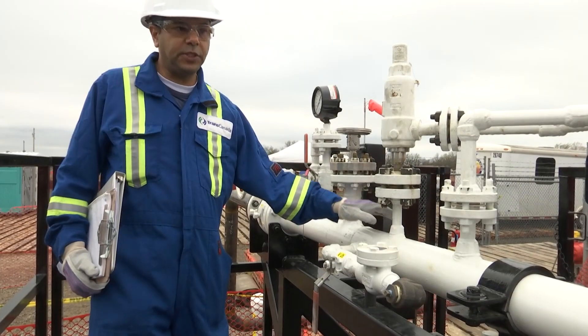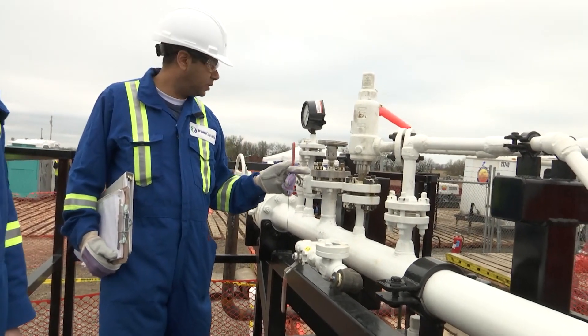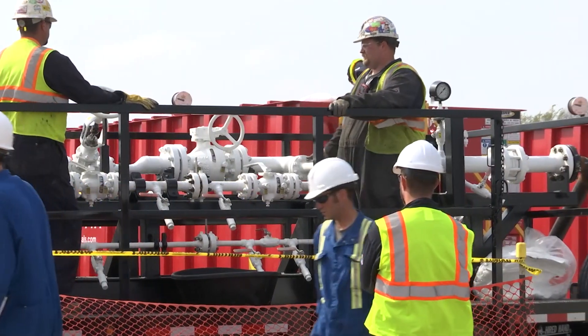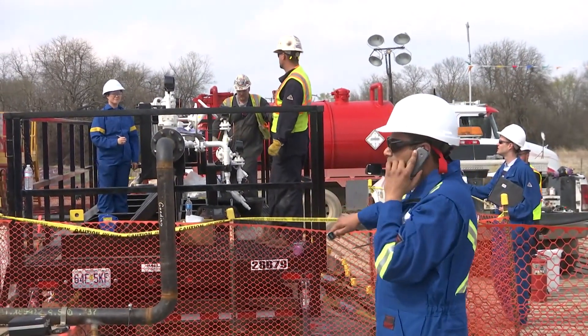When we flow oil, they will see that the oil is leaving the Keystone pipeline and they will know exactly how much is coming out. Over one week, the team conducted 27 withdrawals under a variety of conditions and flow rates. Early results confirmed TransCanada's leak detection sensitivity is being met or exceeded.